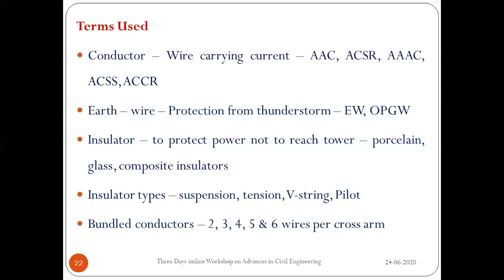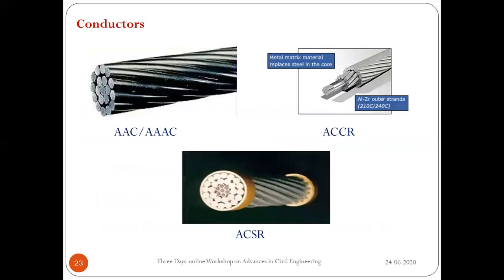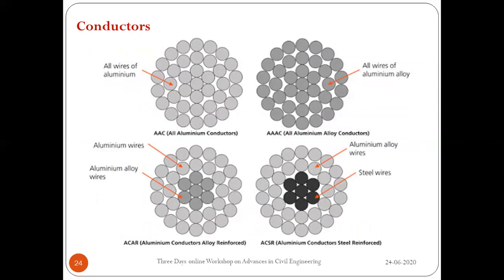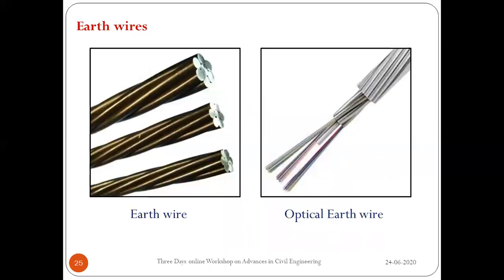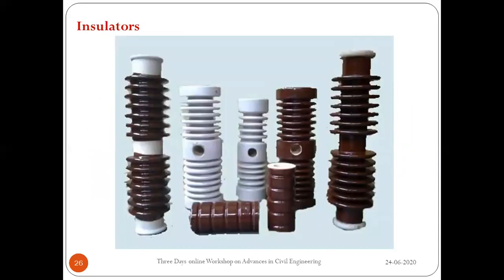Images show different types of conductors used for transmission lines: AAC, AAAC, ACSR, and composite reinforced conductors. Earth wires are shown: the left side is a normal earth wire without optical cables, while the right side is an OPGW (optical ground wire) used for communication in addition to lightning protection. Insulators are typically porcelain, and insulator length increases with the increase in voltage.